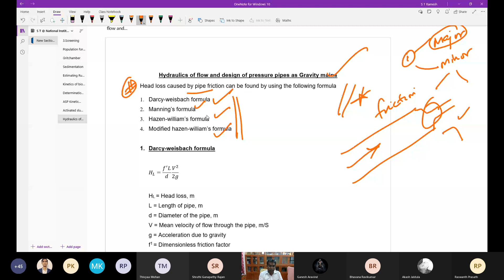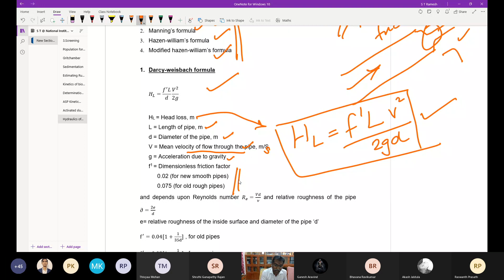HL is equal to F dash L V square by 2GD. This is the formula to calculate friction. Is it okay? Yes, sir. HL is head loss in meters, L is the length of the pipe, D is the diameter, and V is the mean velocity through the pipeline in meters per second. G is acceleration due to gravity, and F dash is a dimensionless friction factor. F dash is 0.02 for a new smooth pipe, and 0.075 for old rough pipes.